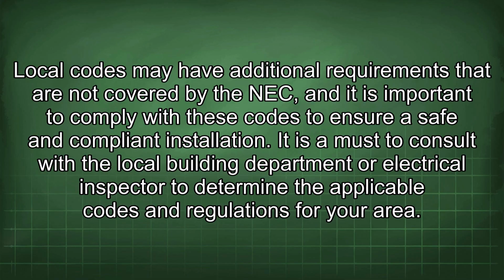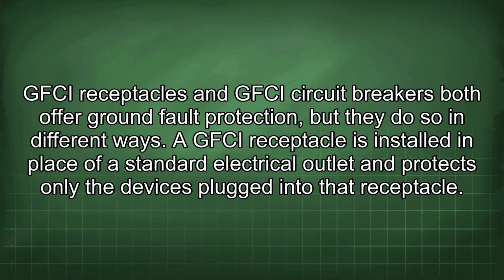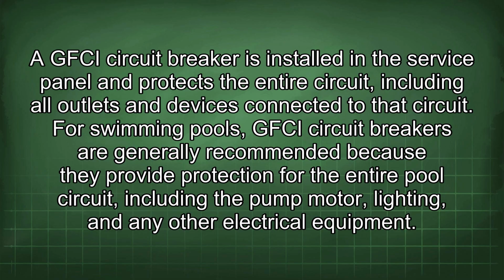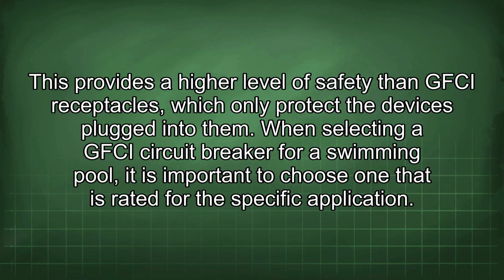regulations for your area. GFCI receptacles and GFCI circuit breakers both offer ground fault protection, but they do so in different ways. A GFCI receptacle is installed in place of a standard electrical outlet and protects only the devices plugged into the receptacle. A GFCI circuit breaker is installed in the service panel and protects the entire circuit, including all outlets and devices connected to that circuit. For swimming pools, GFCI circuit breakers are generally recommended because they provide protection for the entire pool circuit, including the pump motor, lighting, and any other electrical equipment. This provides a higher level of safety than GFCI receptacles, which only protect the devices plugged into them.